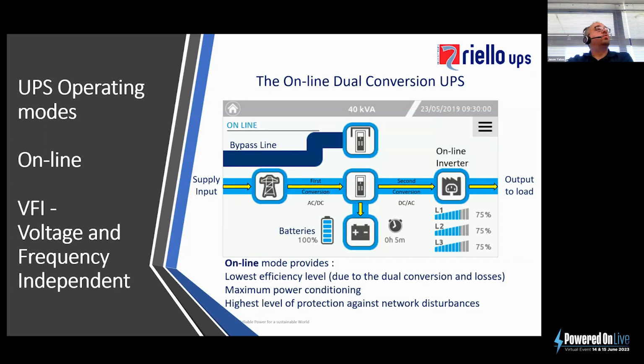Based on this, we can say that the online UPS system provides the very highest levels of protection against any network disturbances, in addition to the maximum power conditioning. The downside of the online dual conversion UPS system is that, because of the conversions taking place within the UPS, it provides the lowest level of efficiency in terms of the operating modes of the UPS system, and so the UPS system has losses.